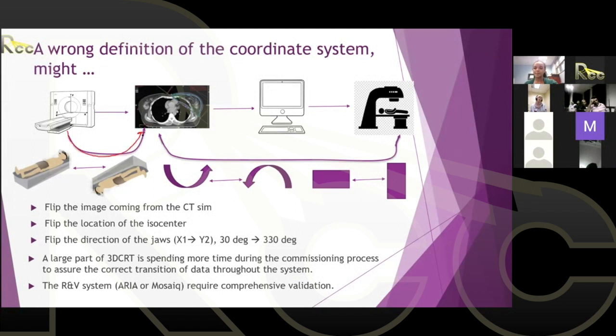Well, this is not a problem because you can always define it from CT sim to the planning system, which is done by the engineer, but you can always do a quick test and verify. You could put a phantom, for example a head, or maybe a square piece or a rectangle piece with a circle piece, and make sure when you send it to the treatment planning system that AP is AP, right is right, and so on.